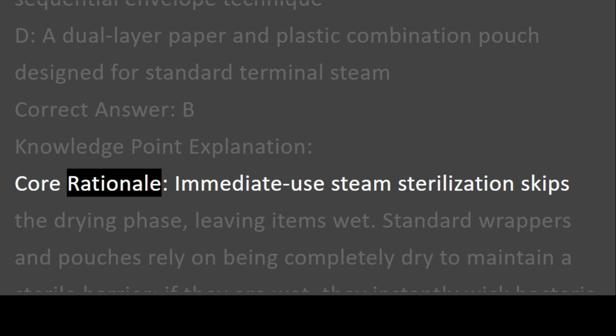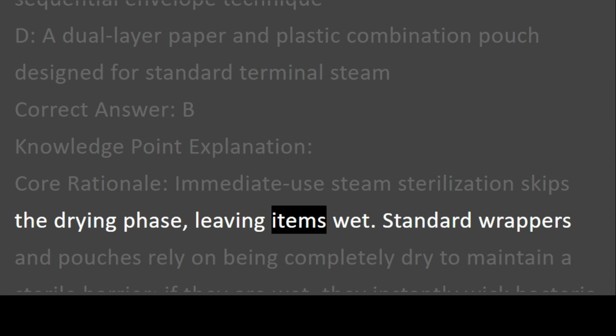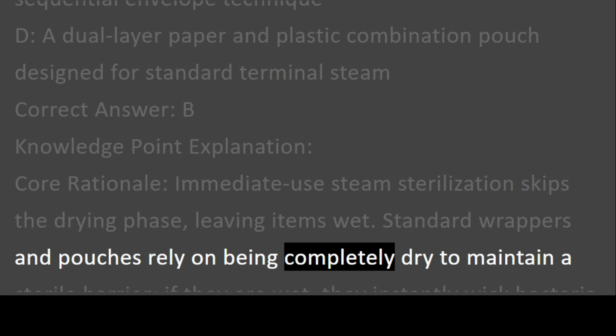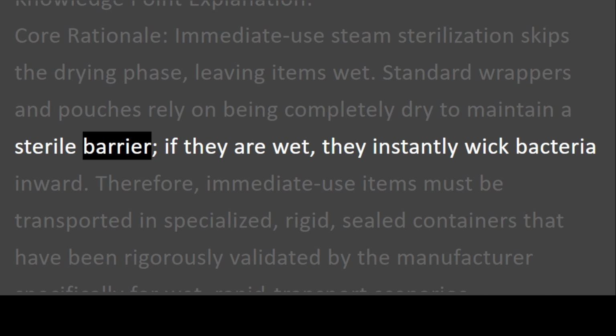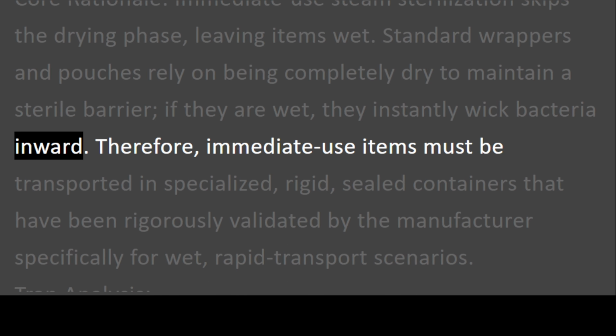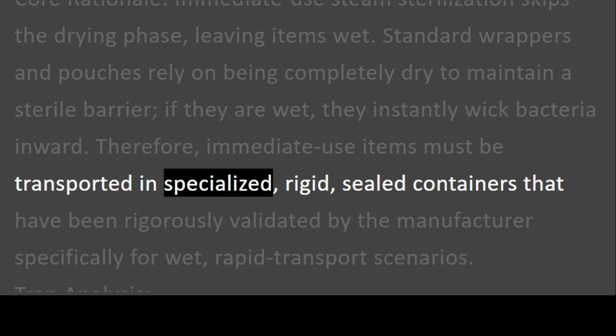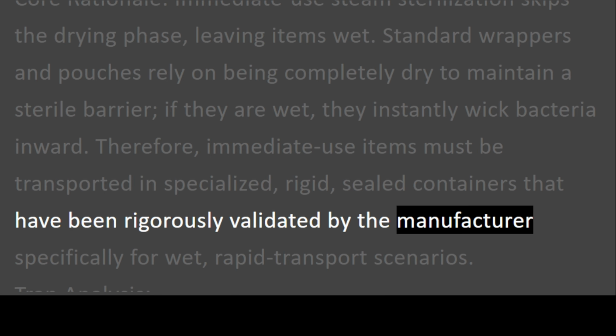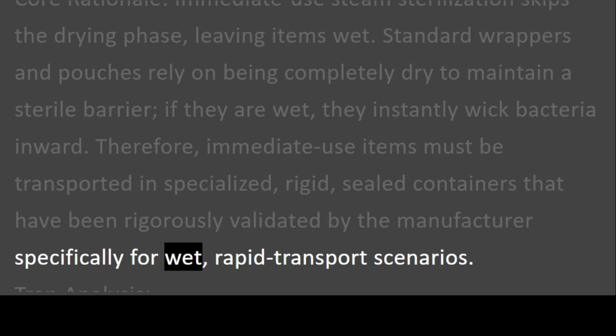Core rationale. Immediate use steam sterilization skips the drying phase, leaving items wet. Standard wrappers and pouches rely on being completely dry to maintain a sterile barrier. If they are wet, they instantly wick bacteria inward. Therefore, immediate use items must be transported in specialized, rigid, sealed containers that have been rigorously validated by the manufacturer specifically for wet, rapid transport scenarios.